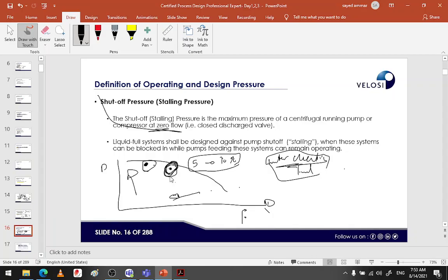Why are we afraid of this? Because sometimes with a centrifugal running pump, especially in LNG activity, most designers go for the operating point and totally ignore the shut-off pressure. This leads to a lot of problems. If you heard about the accident that happened here in Egyptian LNG, it was because of the shut-off pressure of the pump. The pressure increased dramatically in the pipeline, causing the pipeline to rupture. Okay, is it clear?